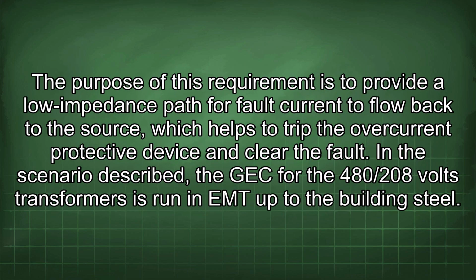The purpose of this requirement is to provide a low impedance path for fault current to flow back to the source, which helps to trip the overcurrent protective device and clear the fault. In the scenario described, the GEC for the 480/208 volt transformers is run in EMT up to the building steel.